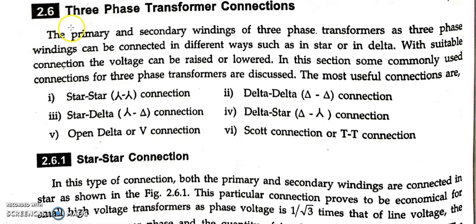Now let us move to the various three phase transformer connections. We have at first star star connection, second delta delta connection, third star delta, fourth delta star, fifth one is open V connection. I told you, if you want three phase connection out of two single phase transformers, then you're going to do V connection or open delta connection. The other one is Scott connection. This is the connection which you use to convert three phase into two phase. Okay, we shall learn one by one.